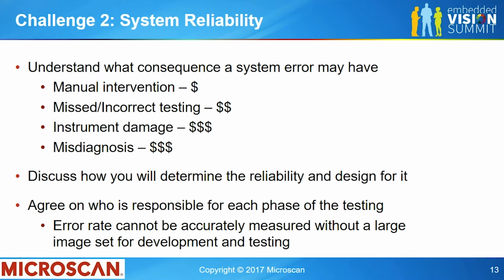Instrument damage. If you say something is a certain height and it's actually different, then you might have some collisions within the instrument and actually damage the instrument. And of course, misdiagnosis, although rare, is the most concerning, whether you're tying results to the wrong patient, or if the vision system itself is looking for 1, 2, 3 lines and actually making the diagnosis, then you really have to make sure that that system's robust.